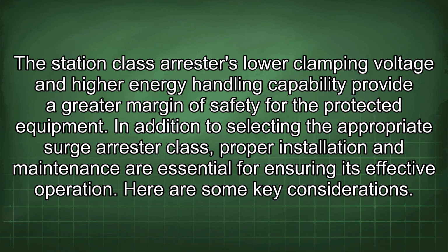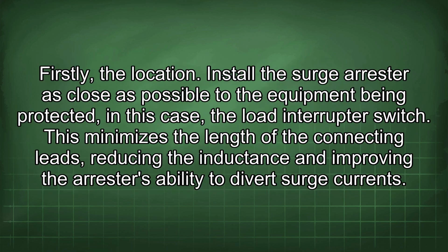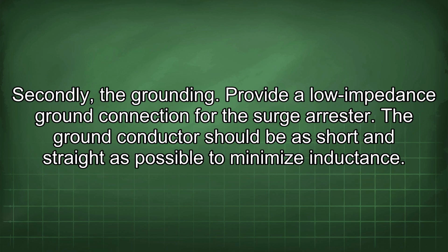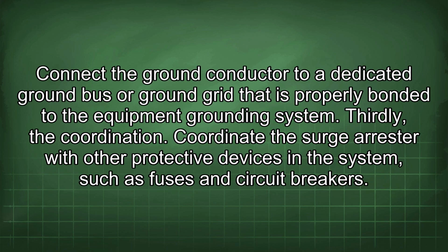In addition to selecting the appropriate surge arrestor class, proper installation and maintenance are essential for ensuring its effective operation. Here are some key considerations. Firstly, the location. Install the surge arrestor as close as possible to the equipment being protected, in this case, the load interrupter switch. This minimizes the length of the connecting leads, reducing the inductance and improving the arrestor's ability to divert surge currents. Secondly, the grounding. Provide a low-impedance ground connection for the surge arrestor. The ground conductor should be as short and straight as possible to minimize inductance. Connect the ground conductor to a dedicated ground bus or ground grid that is properly bonded to the equipment grounding system.